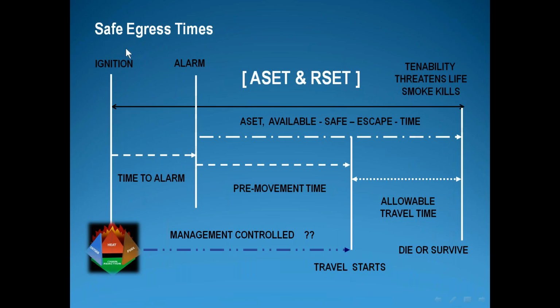Here we can see the start of ignition, the alarm, and we have a certain time to the alarm. So we have to be aware, with the electrical engineer who designed the fire alarm system, of what the response time of the smoke, flame or gas detectors is. We have to know this, and this response time changes according to the level of installation of such detectors. And sometimes if you exceed 9 meters or 12 meters, it's useless to use conventional detectors. You have to find another way to detect that you have smoke or a flame or a fire in a ceiling of such height.